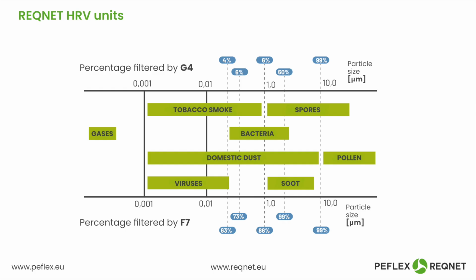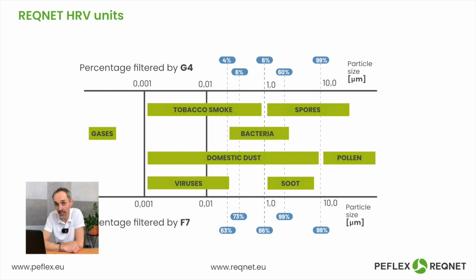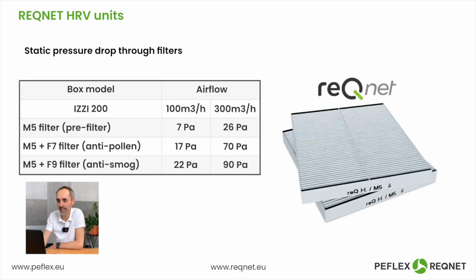So maybe someone can answer this question for me. What's the point of using recuperator devices that control air quality, or that are controlled by air quality? These devices have heat recovery rates of 85, even over 90%. If, in reality, we're bringing in dirty, polluted air by using lower quality class filters? I'm waiting for an answer. I just don't get it.